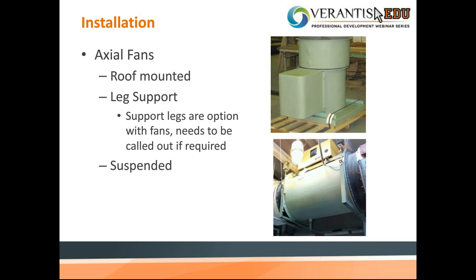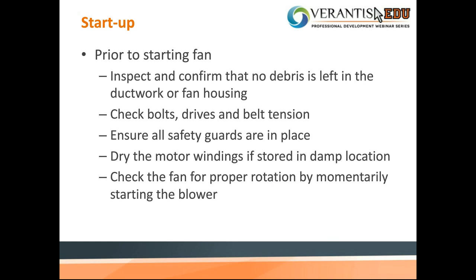All right, let's talk startup. We've got our fan installed. We've got all the checklists ready to rock and roll. So let's do startup. Prior to starting up the fan, inspect and confirm that there is no debris inside the ductwork or the housing. We definitely don't want a chunk of something going through the fan, because we may damage the housing or the impeller. Check all bolts, drives, and belt tension.